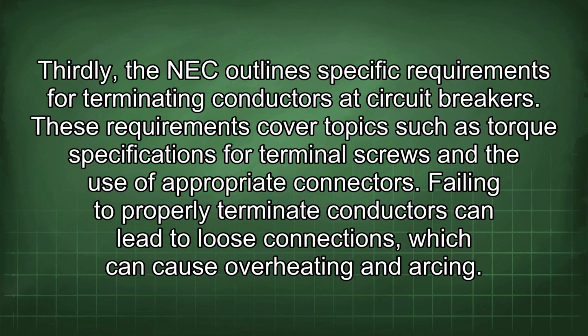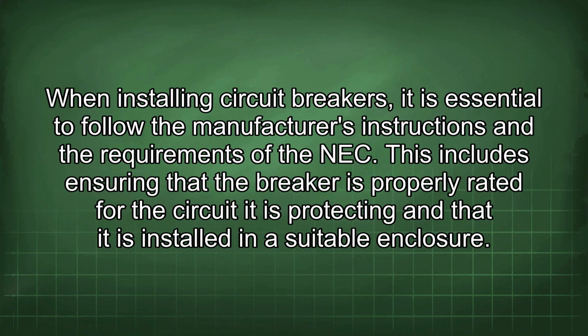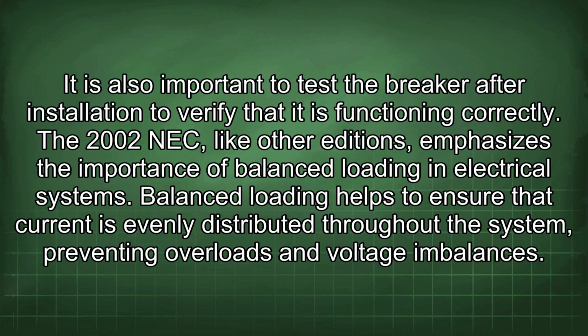Thirdly, the NEC outlines specific requirements for terminating conductors at circuit breakers. These requirements cover topics such as torque specifications for terminal screws and the use of appropriate connectors. Failing to properly terminate conductors can lead to loose connections, which can cause overheating and arcing. When installing circuit breakers, it is essential to follow the manufacturer's instructions and the requirements of the NEC. This includes ensuring that the breaker is properly rated for the circuit it is protecting and that it is installed in a suitable enclosure.